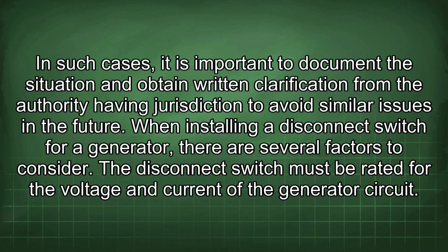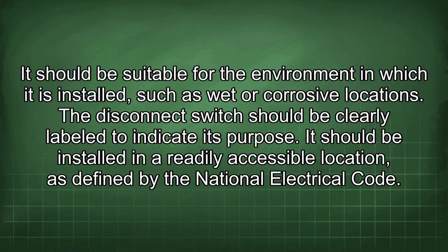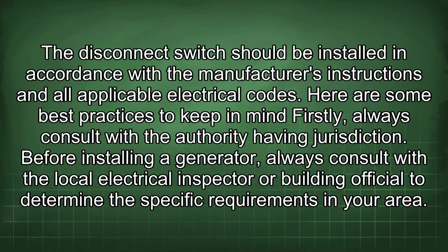When installing a disconnect switch for a generator, there are several factors to consider. The disconnect switch must be rated for the voltage and current of the generator circuit. It should be suitable for the environment in which it is installed, such as wet or corrosive locations. The disconnect switch should be clearly labeled to indicate its purpose. It should be installed in a readily accessible location, as defined by the National Electrical Code. The disconnect switch should be installed in accordance with the manufacturer's instructions and all applicable electrical codes.